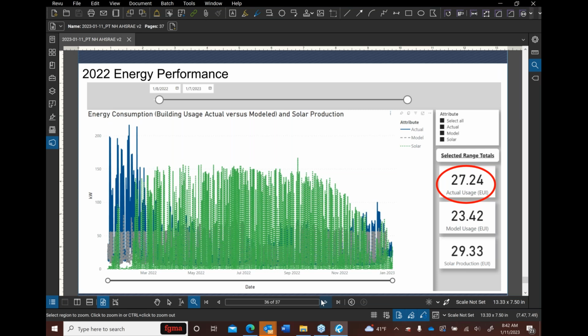Yeah. And one thing, commissioning, guys, did you do full commissioning on the building? It sounds like you must have. You did blower door testing for sure. We did. Yeah, we did full commissioning, and I think they caught a lot of the items. But like we said, one of the items that was not caught was, I guess this is a good time to talk about this. If you look at the chart that's shown here, to the way left is the start of the year in January of, what would that be, 21? 22. No, 22, thank you, January 22. And then to the right is January of 23. And so on the left the blue indicates the amount of energy that we used. And you can see that we're much higher than what we had anticipated in the gray.